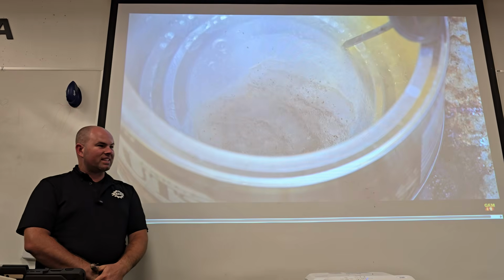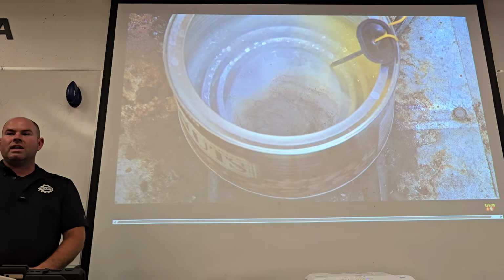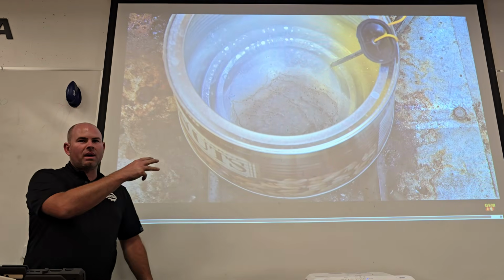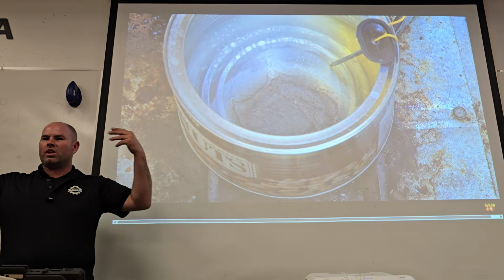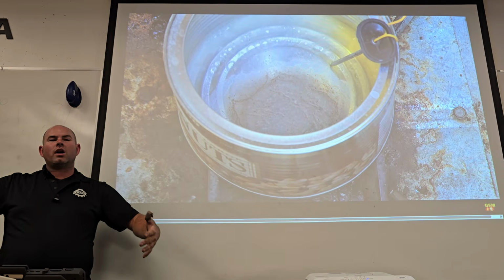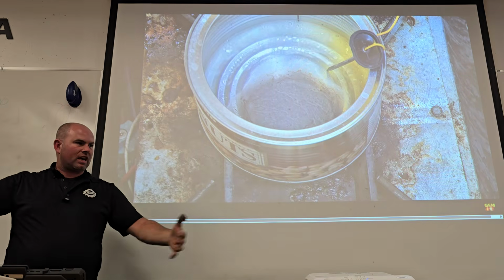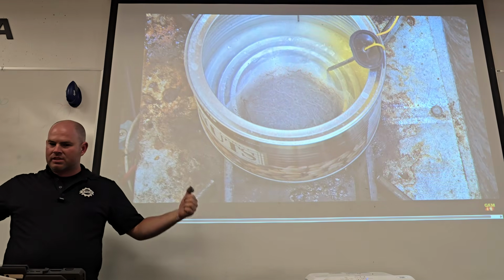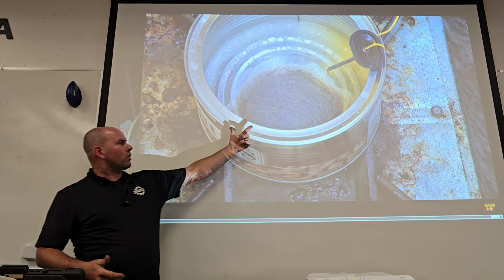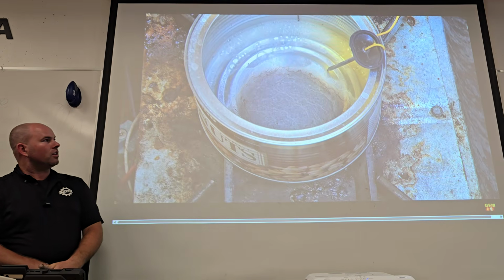It's starting to burn it. Why is that? Now the BTUs are going to heating the metal rather than the BTUs going to boiling the water. Make sense? The water, remember, the water grabs the heat as it changes to a vapor. That's what the evaporator does. It grabs the heat. Now there's not enough water to grab the heat and it's burning this thing. You can see it, right?